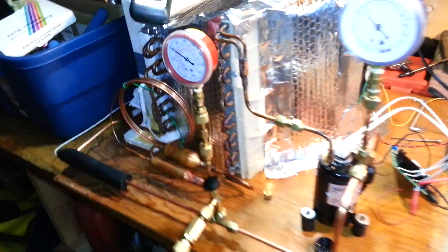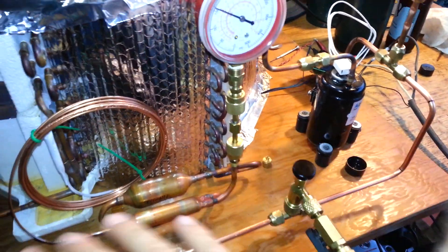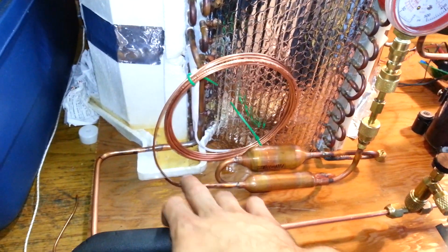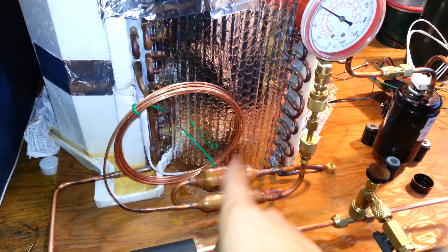So I am going to remove the refrigerant, evacuate it, because I'm going to do some brazing, so I want to get all the propane out. I don't want to have a fire. I'm going to unbraze the cap tube here, pull it out, remove some certain amount of the cap tube.